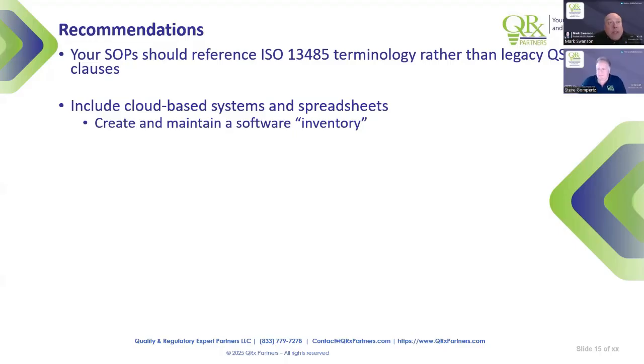And we recommend this to all of our clients because one of the first questions that an inspector, or an auditor for ISO 13485, is going to ask is, where's the validation of your software in your QMS? What software do you validate? If you have that inventory list, it's an easy answer. If you don't, then you're going to go, I don't know, maybe, what do we have? It's much easier to answer that question if you have that ready list.